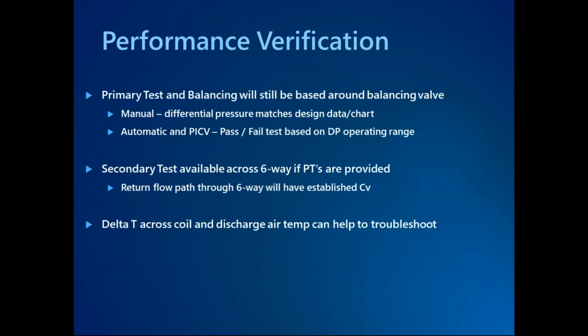So first and foremost, we're going to want to measure the differential pressure across the balancing valve if a balancing valve is present. If it meets the design differential pressure that the manual balancing valve is provided with in terms of the tag or the chart or the wheel, whatever it might be, you're balanced. And then automatic balancing valves and PICVs are just going to be a pass-fail test to make sure that the differential pressure is within the operating range of these valves.